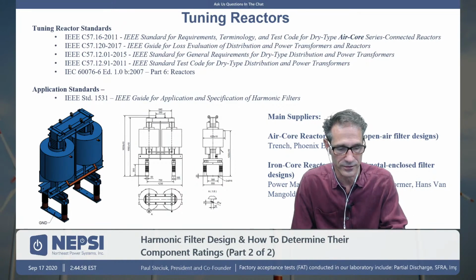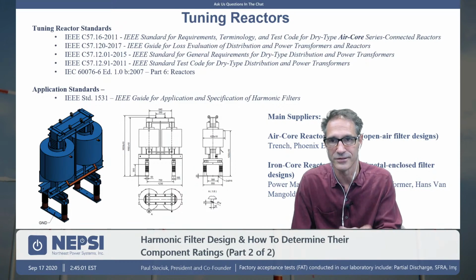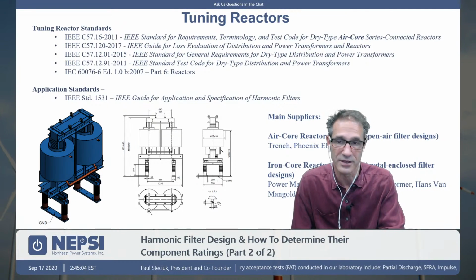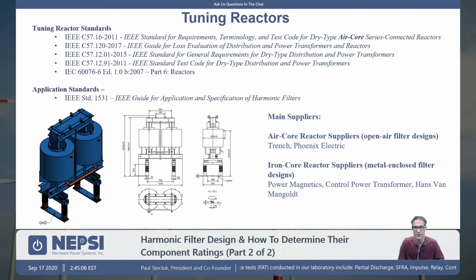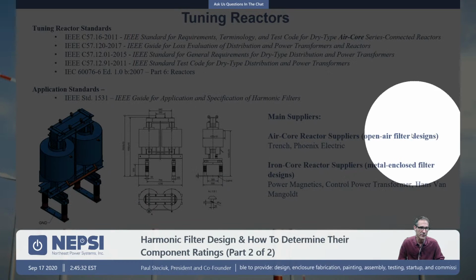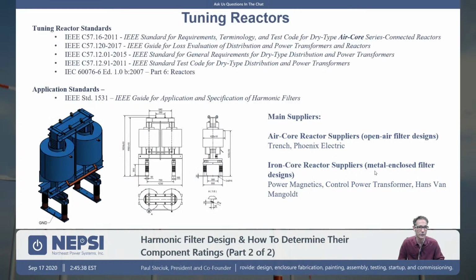The most difficult part in the design of a harmonic filter is the iron core reactor. It's not to be taken lightly, the design of that and the selection of the manufacturer of that iron core reactor, and also the ratings of the iron core reactors. So we had another tech talk that talked about iron core reactors. I would recommend that before you specify iron core reactors, go back and watch that presentation. It would be good for you to do that. So air core reactors, you're going with an open air filter. You basically are dictating what type of filter you have if you want an air core reactor. And iron core reactors, you're always going with a metal enclosed design.